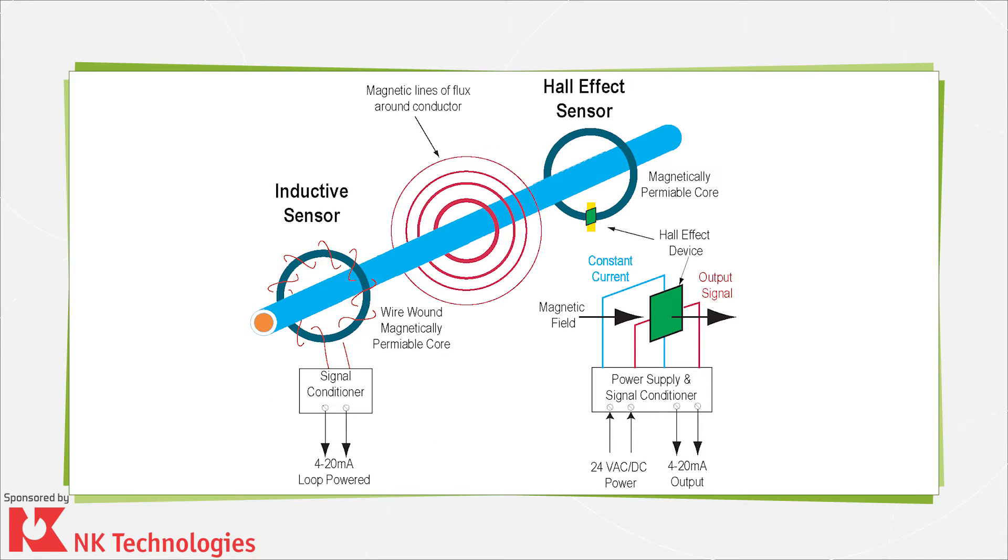To get an idea of how these current sensors work, consider a typical Hall effect sensor. A wire carrying the DC current goes through a magnetically permeable core, which is there to concentrate the wire's magnetic field. The Hall effect device sits in the core cross section at a right angle to the concentrated magnetic field. A constant current from the power supply excites the Hall device. When the energized Hall effect device is exposed to a magnetic field from the core, it produces a voltage that can be measured and amplified.